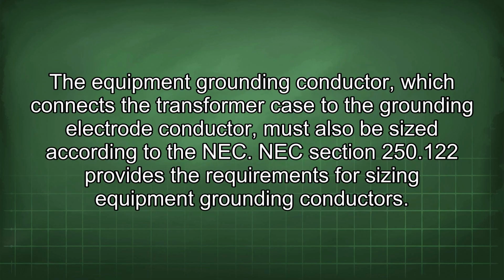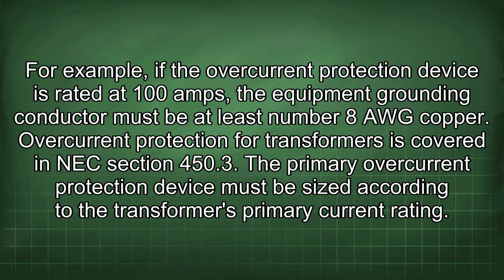The equipment grounding conductor, which connects the transformer case to the grounding electrode conductor, must also be sized according to the NEC. NEC Section 250.122 provides the requirements for sizing equipment grounding conductors. For example, if the overcurrent protection device is rated at 100 amps, the equipment grounding conductor must be at least number 8 AWG copper. Overcurrent protection for transformers is covered in NEC Section 450.3.